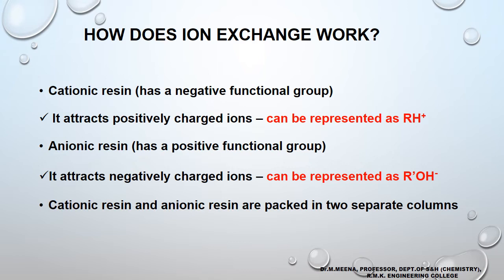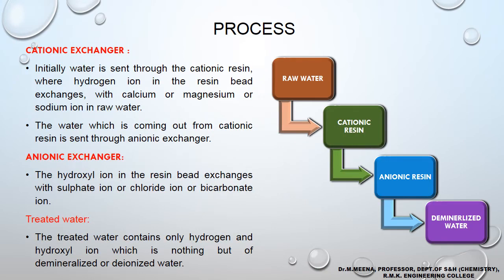The cationic resin attracts all positively charged ions, and the anionic resin attracts all negatively charged ions. These two resins are packed in two separate columns. Raw water containing hardness and non-hardness causing salts is first sent into the cationic resin column where all cations are exchanged. The water coming out of the cationic column is then sent into the anionic resin column where all anions are exchanged, and finally we obtain demineralized water.